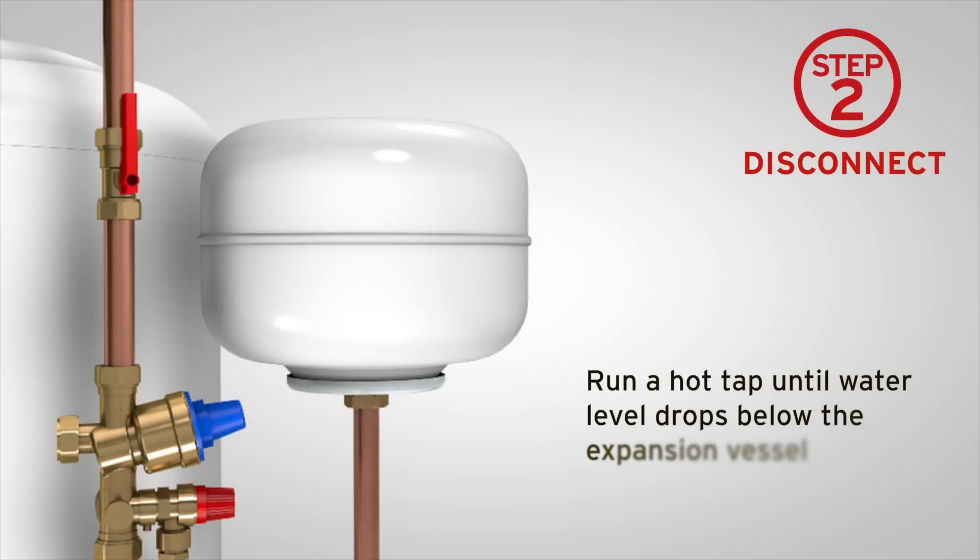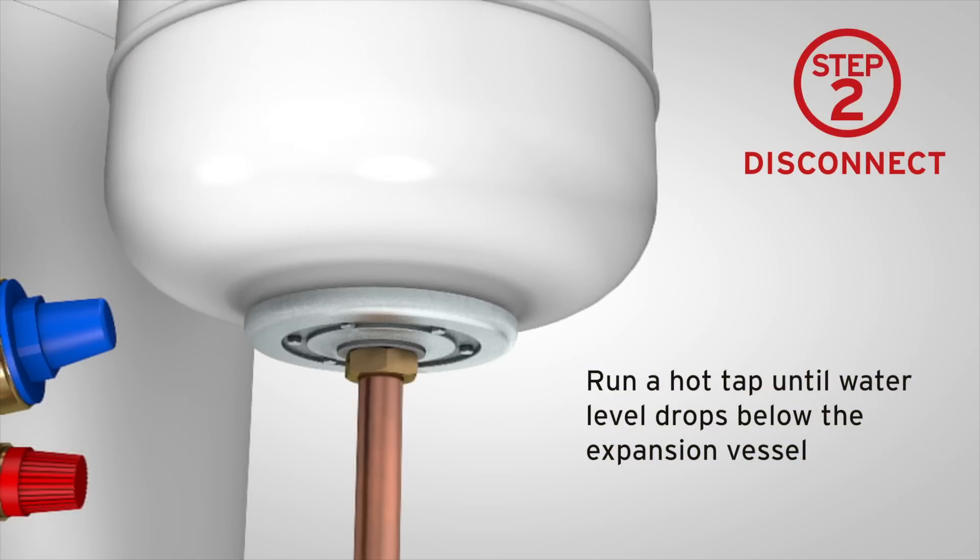Step 2: Assuming initial checks are all OK, you need to isolate and depressurize the cylinder, then physically disconnect the expansion vessel from the system.